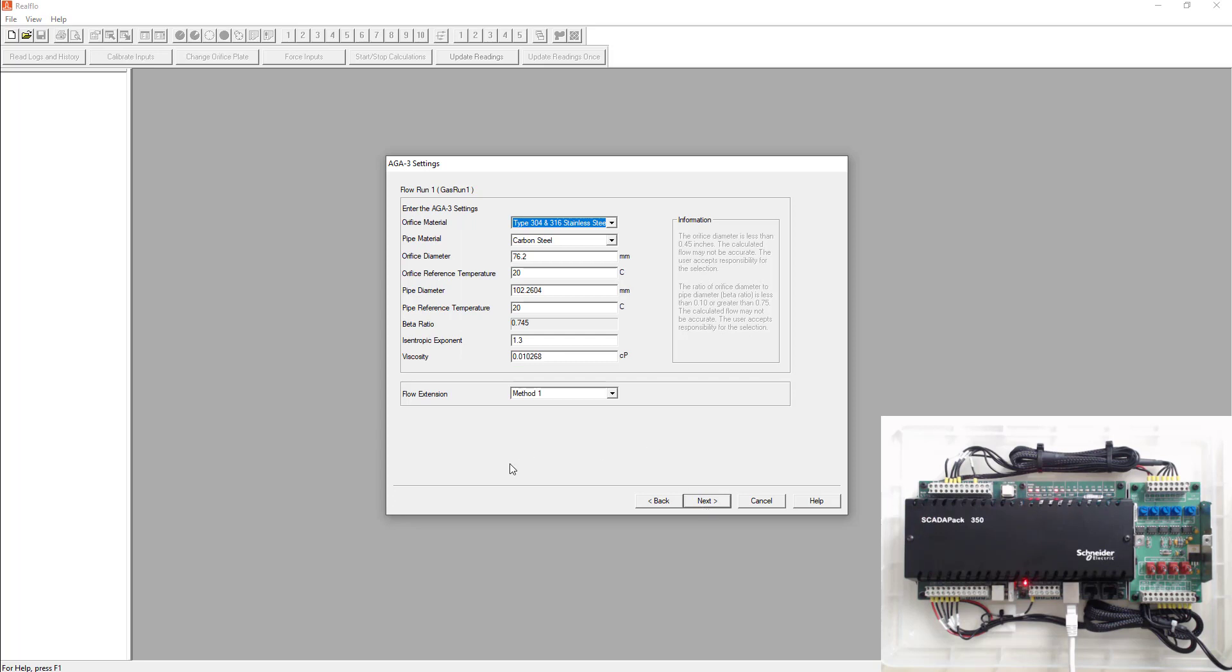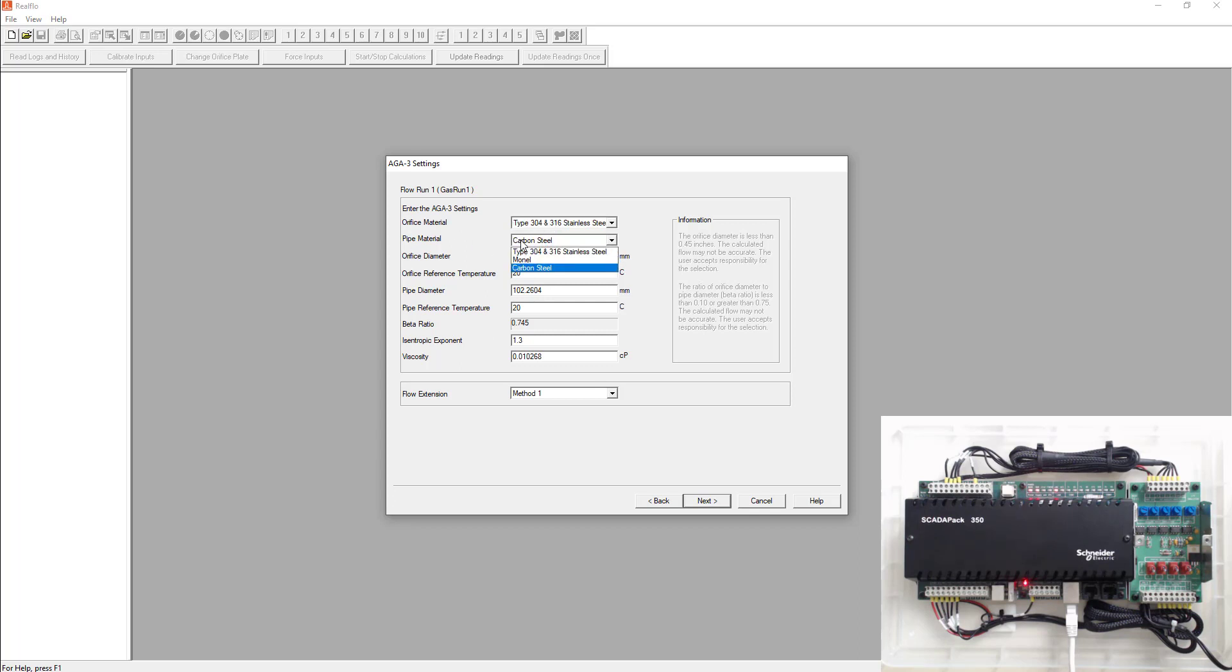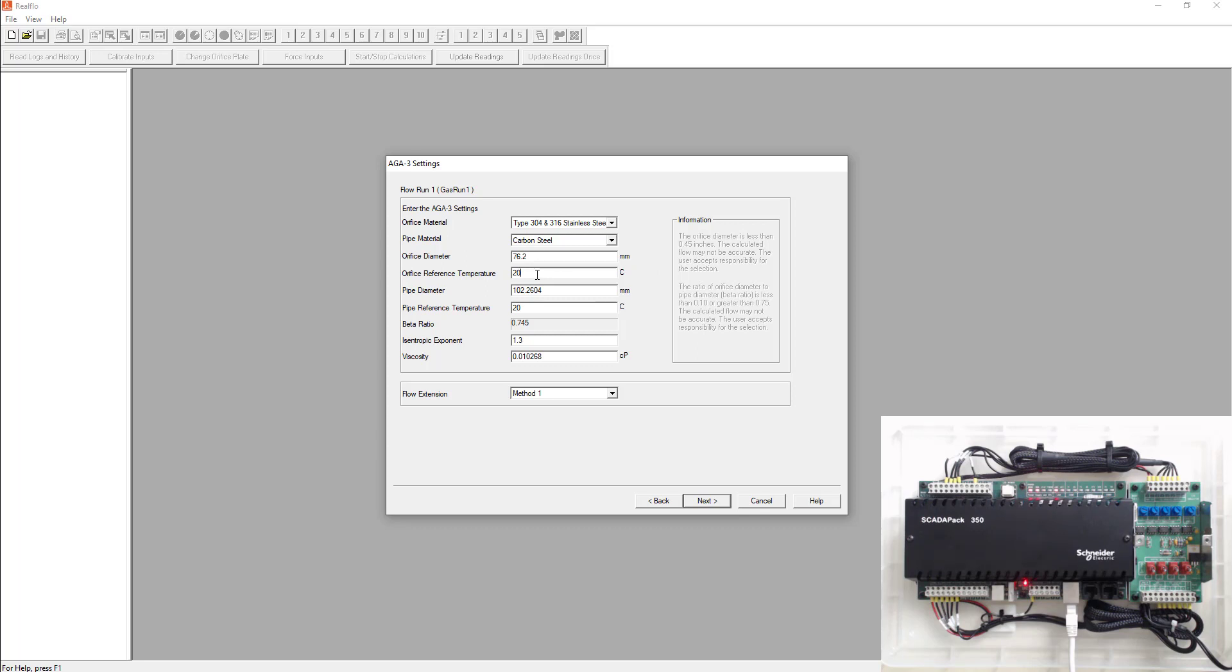Once you put your gas composition in, you could go ahead, put your orifice plate material. Typically, it's always stainless steel, your pipe material. Typically it's always carbon steel, your orifice plate diameter. Typically they come in inches. You have to calculate that into millimeters. Orifice reference temperature is typically always 20. Your pipe diameter, same thing. Again, you take your pipe diameter, put it into millimeters. Your typical pipe reference temperature is always typically always 20 and then leave the rest as is and go next.